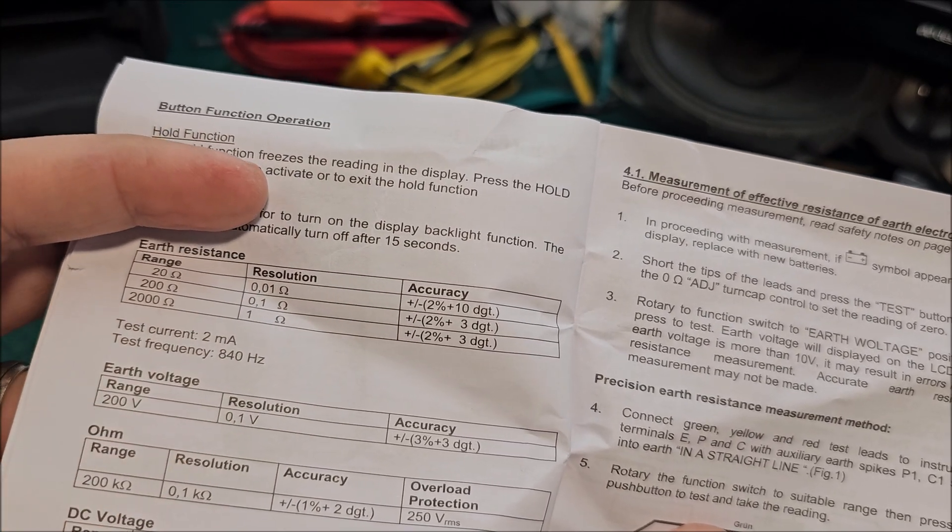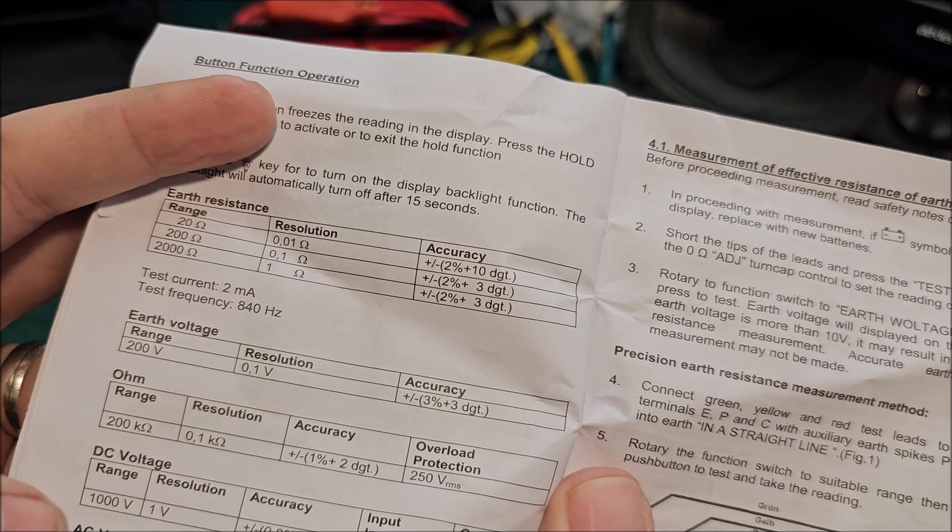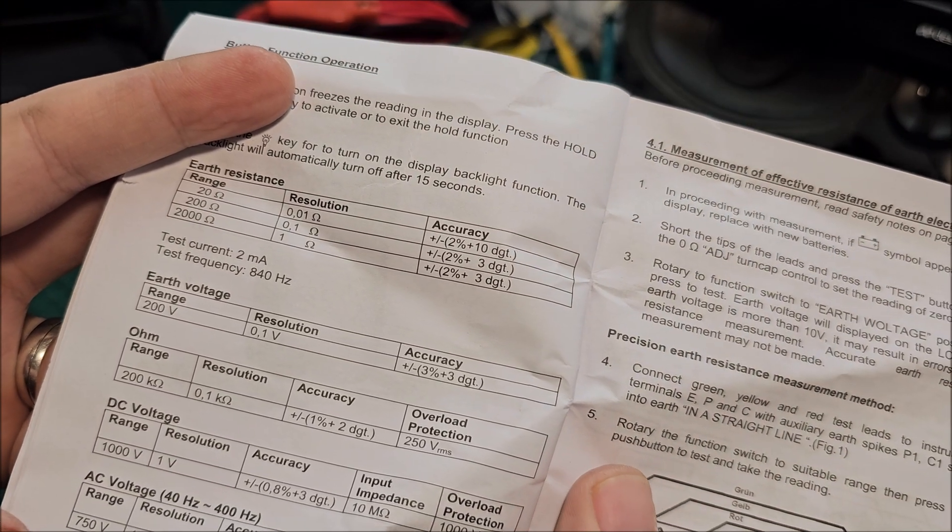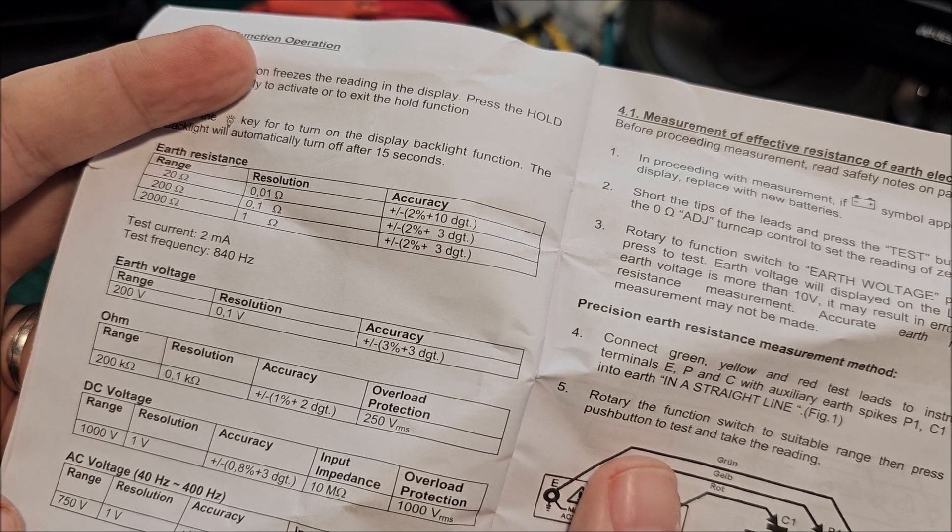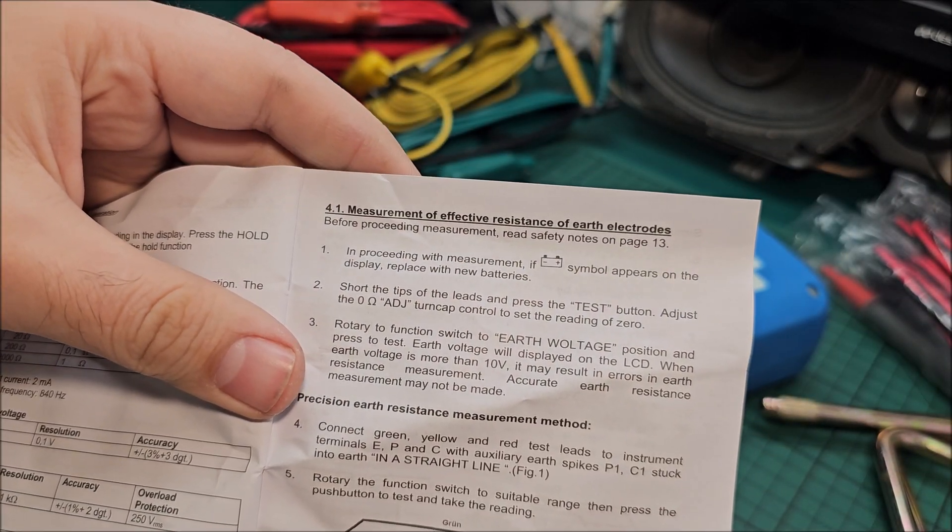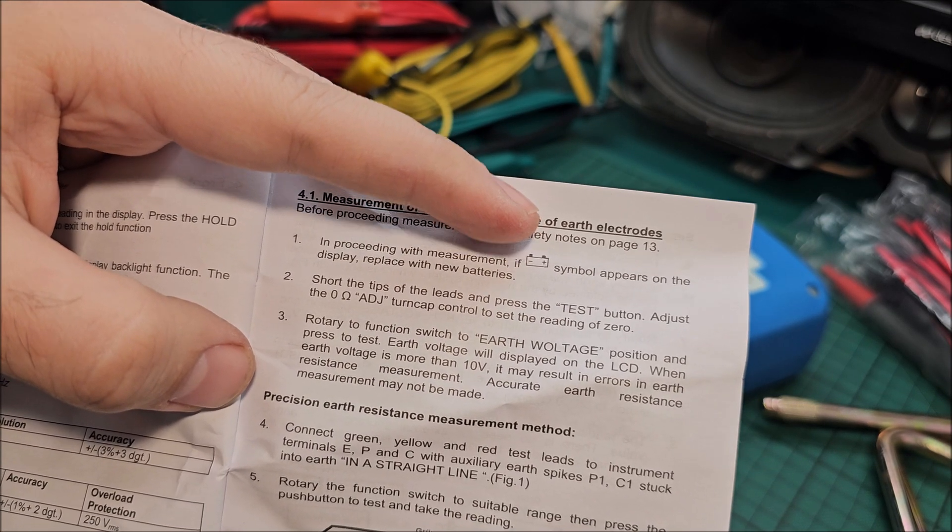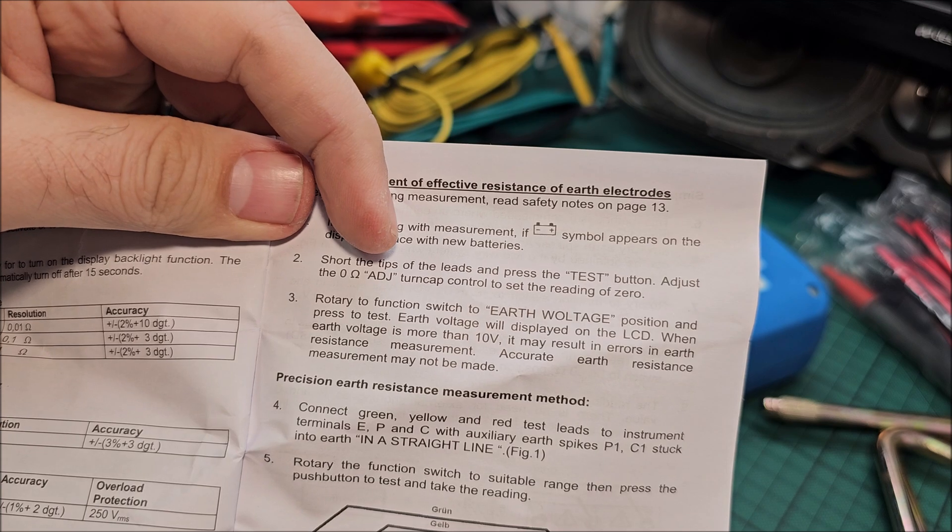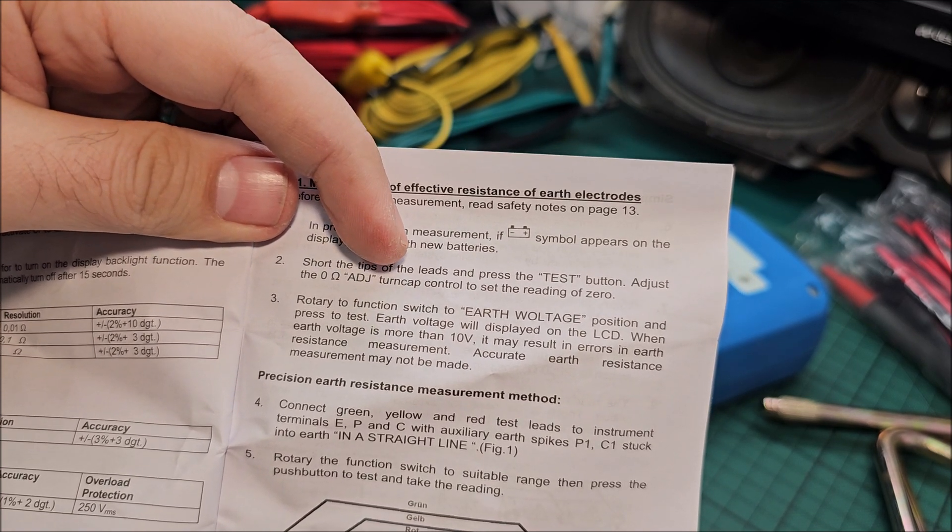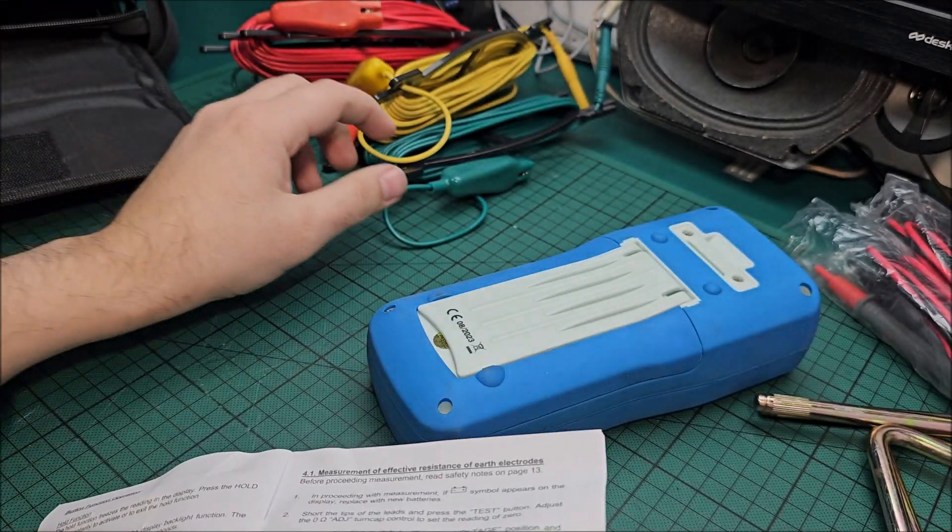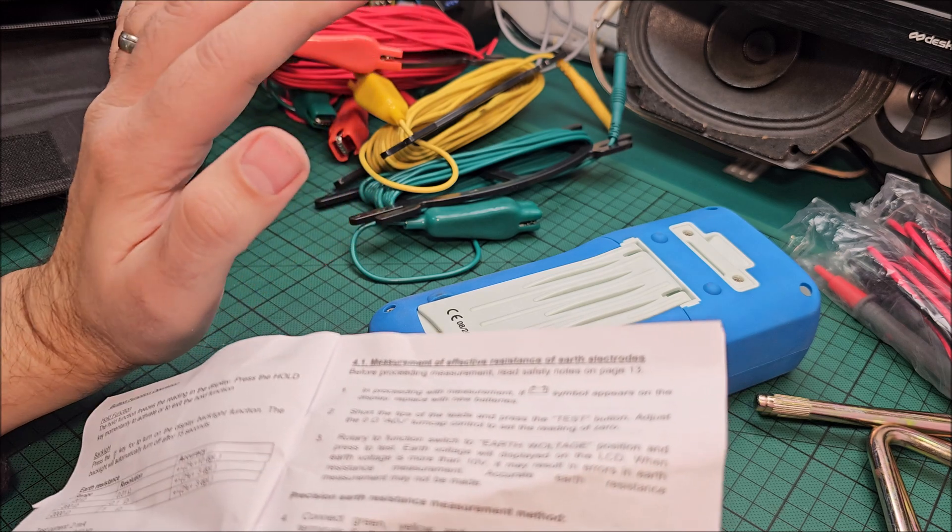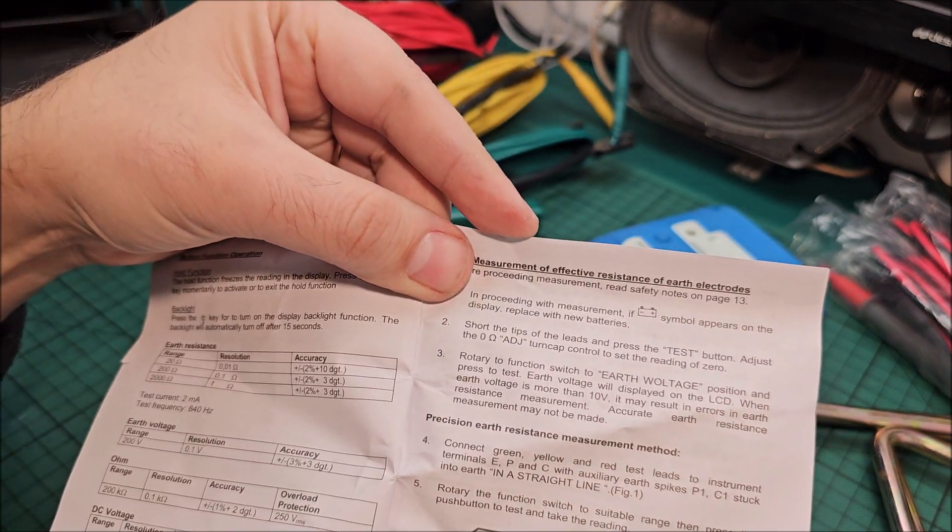Okay, so hold function, backlight, yep, range and the resolution of it and accuracy. So accuracy is actually the important thing, the resolution a bit less important. Earth voltage, DC voltage, AC voltage, so it can actually measure even DC and AC. If that gets on the display, you need to put in new batteries. Short the tips and press test, and you adjust to zero so then you compensate for the clips, for the cables, for everything.